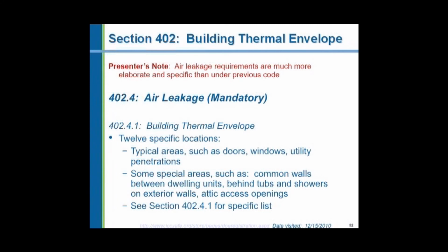Section 402 now talks about the air leakage of the building. We talked about air leakage of the windows moments ago. Now we're looking at the entire building. And the new code gets very specific about leakage, reducing infiltration, reducing air changes. And they want you to look at places you possibly never thought of before, such as in a duplex home. What about the demising wall between the 2 dwelling units?